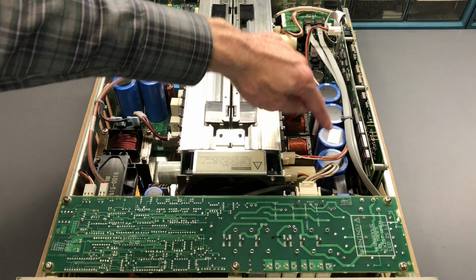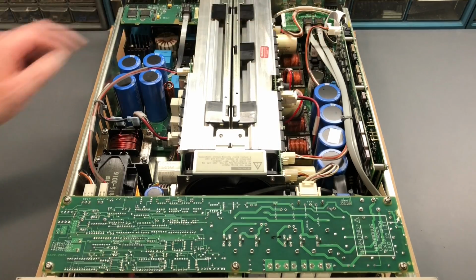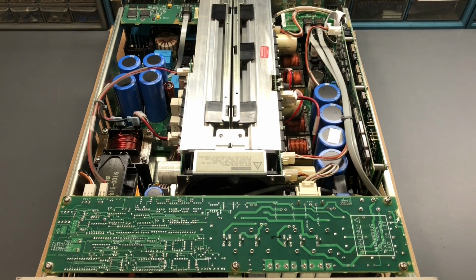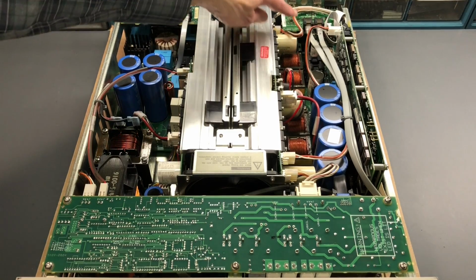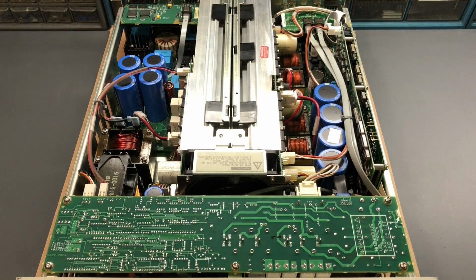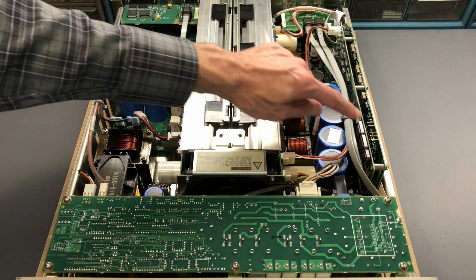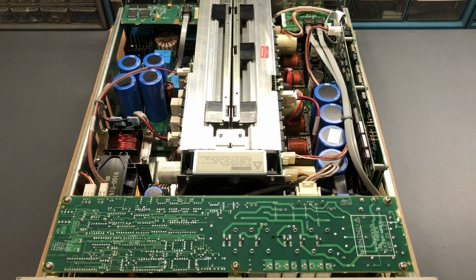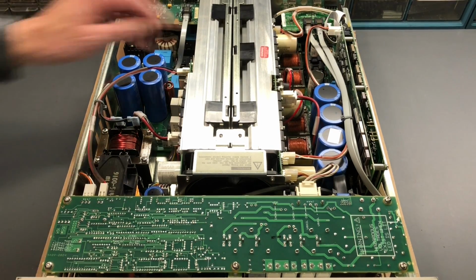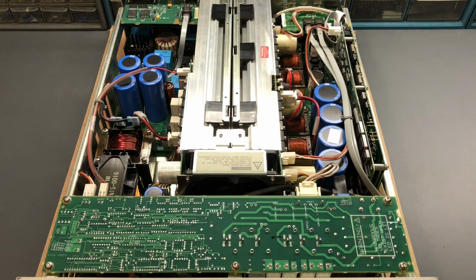Now over here, these large electrolytic capacitors are part of a circuit board down on the bottom, and that circuit board is the output filter and relay assembly. This back corner where these two gray cables with the RJ45 connectors go, that's the trigger assembly, just some auxiliary functions on that. This circuit board right here is the digital signal processor, or DSP, and on the other side this is the main control card right here. And we already saw inside the front panel, which is just slightly out of view up here. And there's a processor within that front panel, and obviously the display and the keypad. So let me grab the block diagram and we'll just run through real quick and see exactly how this instrument functions.